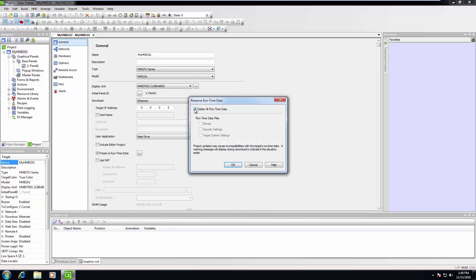Target system settings including network config menu items, IP address, subnet mask, default gateway, DHCP, etc. will be replaced. Uncheck the delete all runtime data checkbox and the data types that have the checkbox ticked will be preserved. Recipe data and security settings will be preserved while the target system settings will be replaced with the project settings.